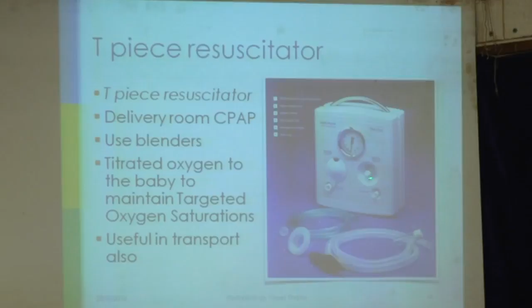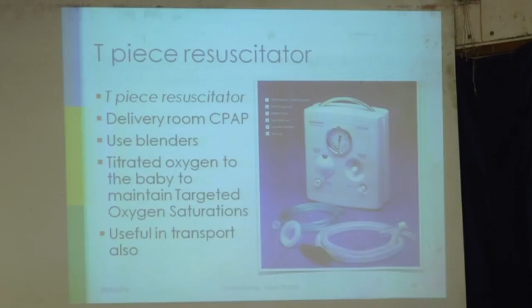The flow is usually kept around 10 to 12 liters. And then we need to set the PIP. We have a knob here, which will help to set the desired inspiratory pressure. The inspiratory pressure is visible here. So once the oxygen flow is generated, we connect these tubings. This tubing will go to the oxygen source or to the air oxygen blended source. This end is to be connected to the universal endotracheal tube, the universal ET connector.